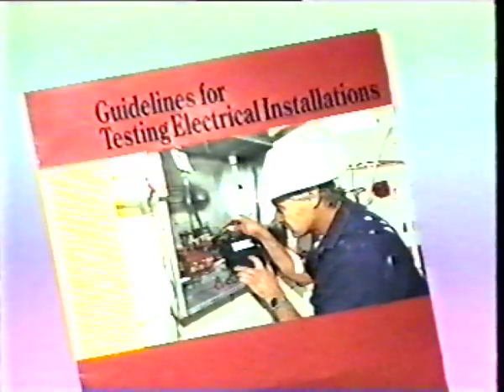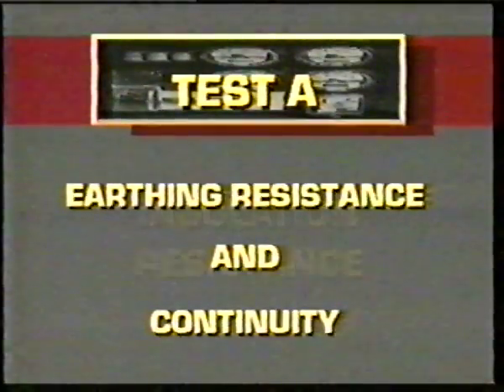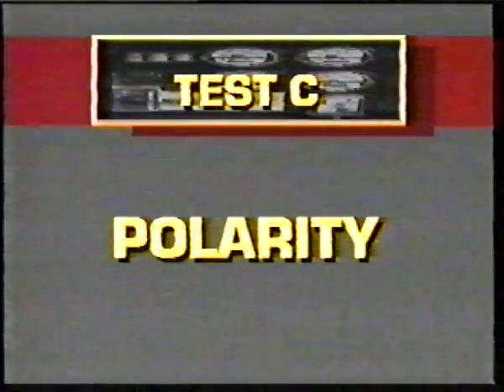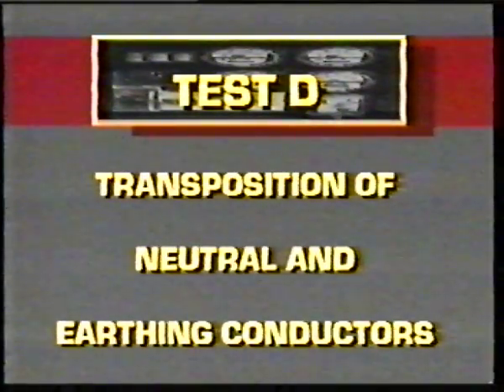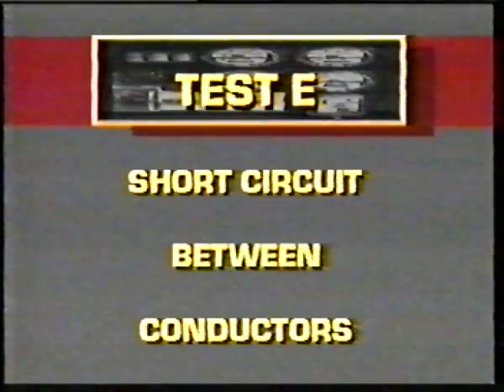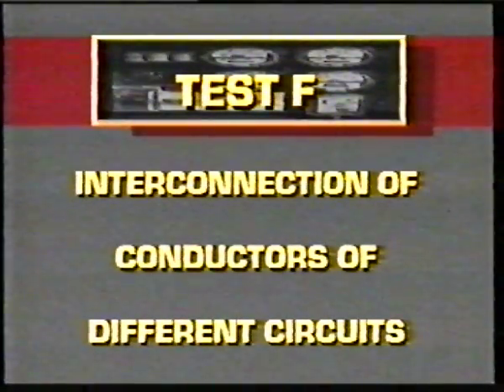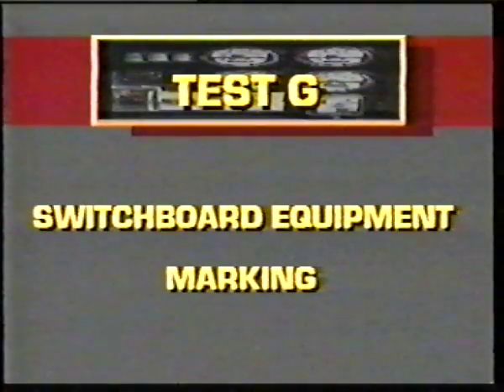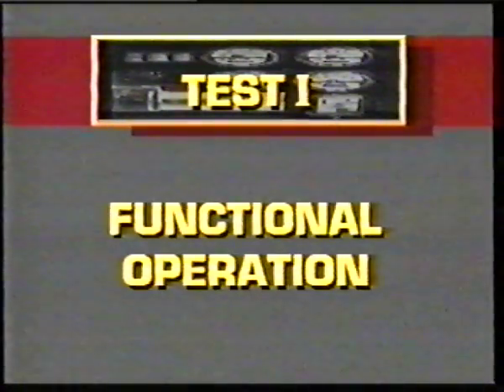Now let's look at the test methods as shown in the document Guidelines for Testing Electrical Installations. The 9 tests required are earthing resistance and continuity, insulation resistance, polarity, transposition of neutral and earthing conductors, short circuit between conductors, interconnection of conductors of different circuits, switchboard equipment marking, number of points per circuit, functional operation. These tests will first be demonstrated under the conditions where supply is not available. At the conclusion of that demonstration, we'll show those tests which can be performed where supply is available.